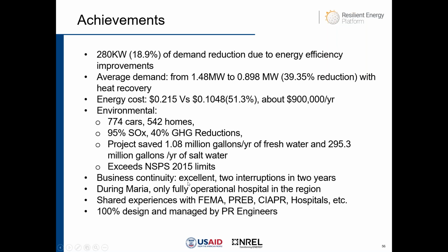The business continuity experience through Hurricane Maria was uninterrupted, but through 3 years of operation we have had only 2 interruptions, and they were not big things. One was a seal on one of the pumps that leaked, so the jacket water was discharged and pump operation was interrupted, which interrupted the engine. The other was a belt issue on the dome radiator.